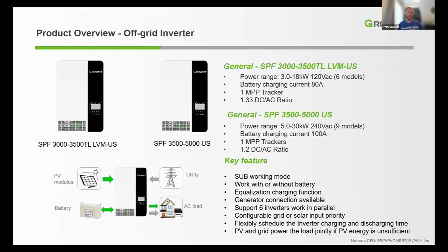And the M would indicate an MPPT controller. You will see that across our product line just to ensure maximum efficiency and output of your PV strings. Obviously, like most string inverters, you do want to coordinate your panel arrays and strings by azimuth. You would generally want to avoid east and west facing panels in the same string just to ensure maximum power output.